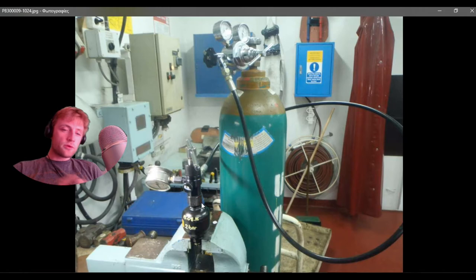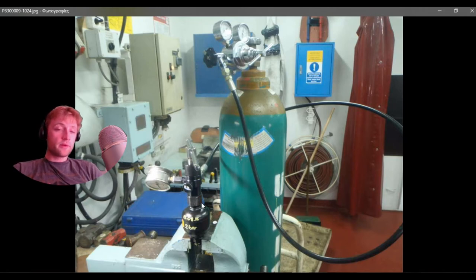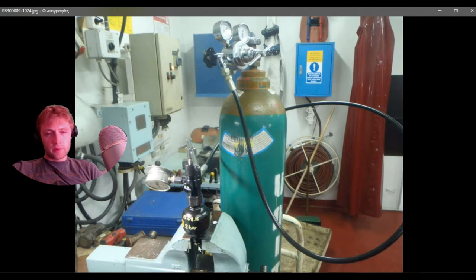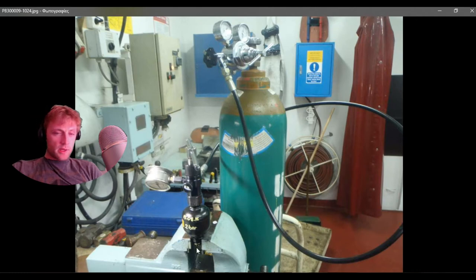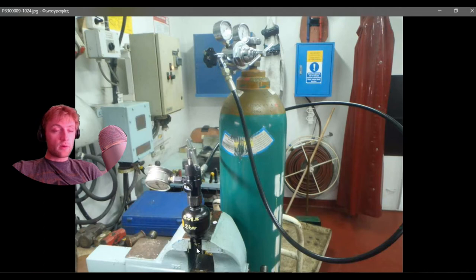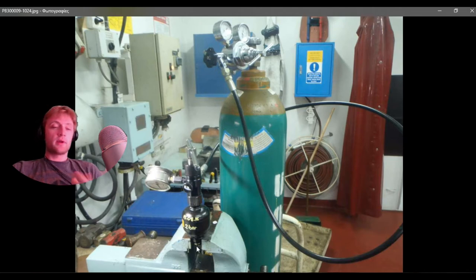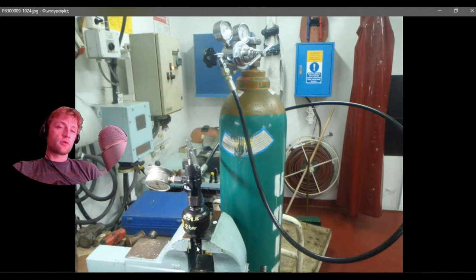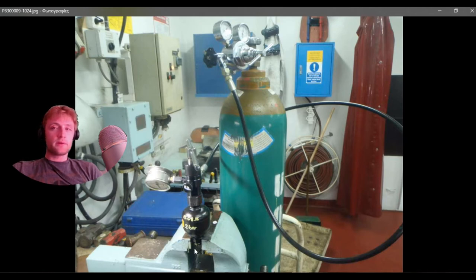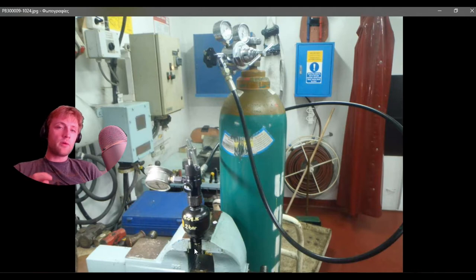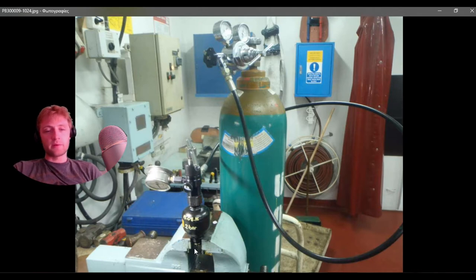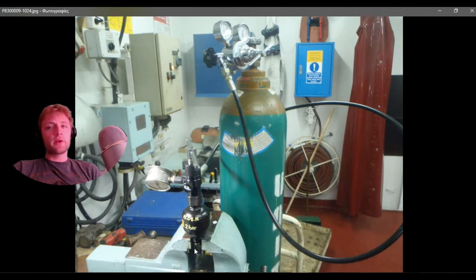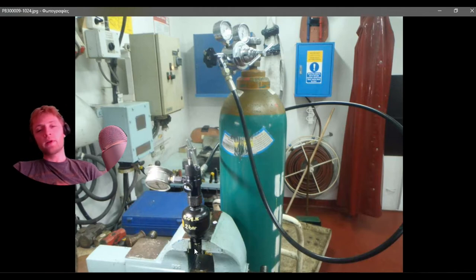What checks are you doing then? You put your finger below here and check if oil or air is coming. At the first moment oil will come for sure, which is accumulated here, but you must wait until all the oil is drained from inside.